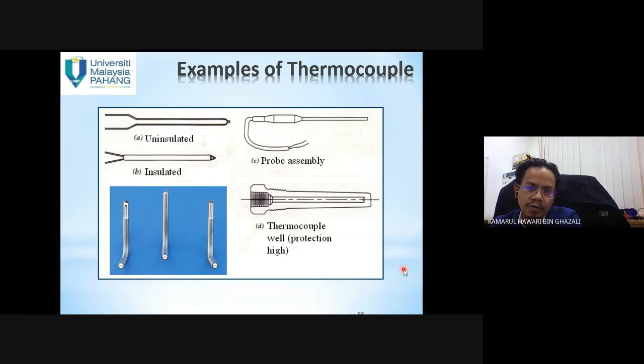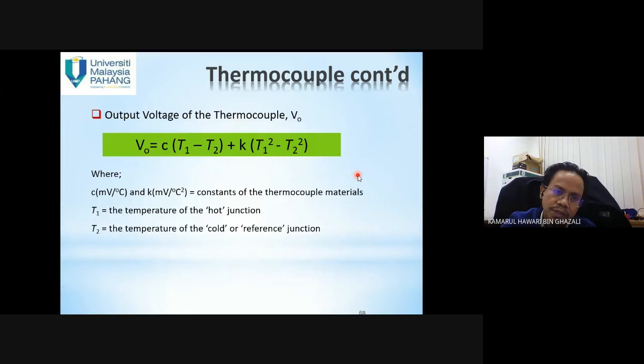So this is the other type of thermocouple: insulated and uninsulated. Insulated means they are covered with some material, probe assembly, thermocouple well protection. So this is how the thermocouple works. Okay, so this is the equation. The difference between A and B produces the voltage. To calculate the voltage, this is the formula.